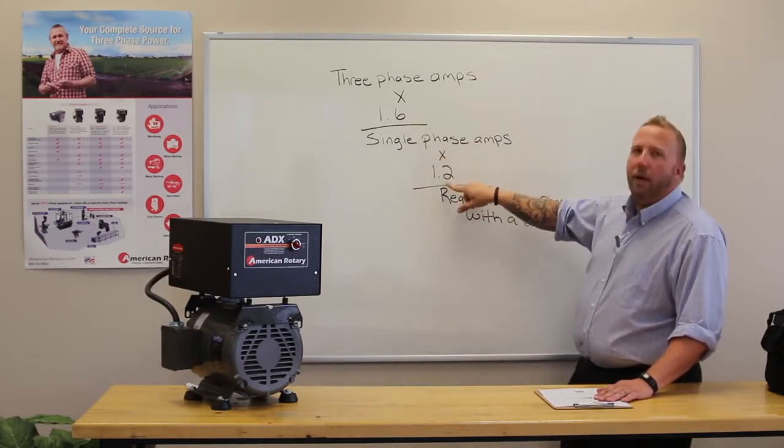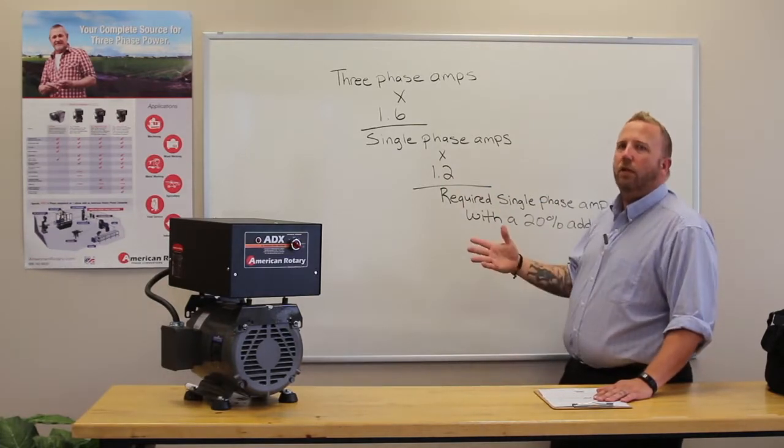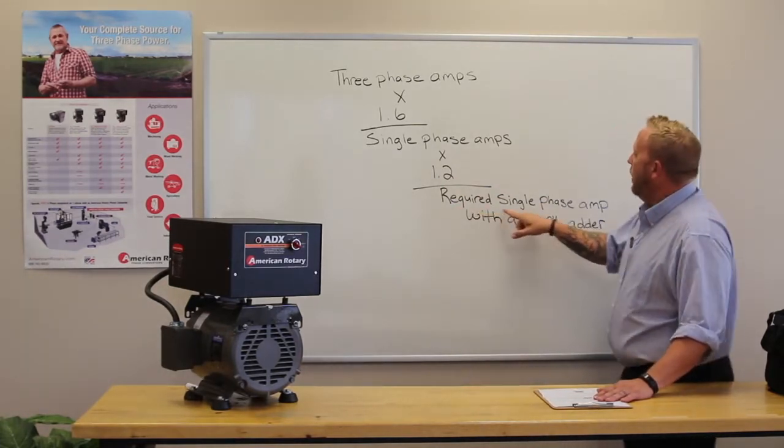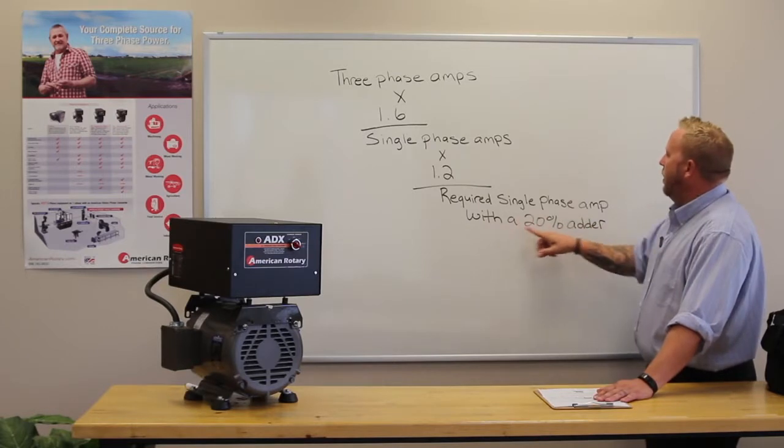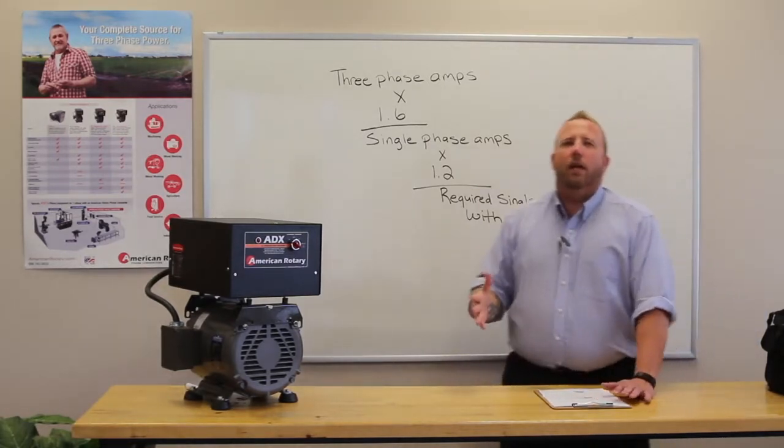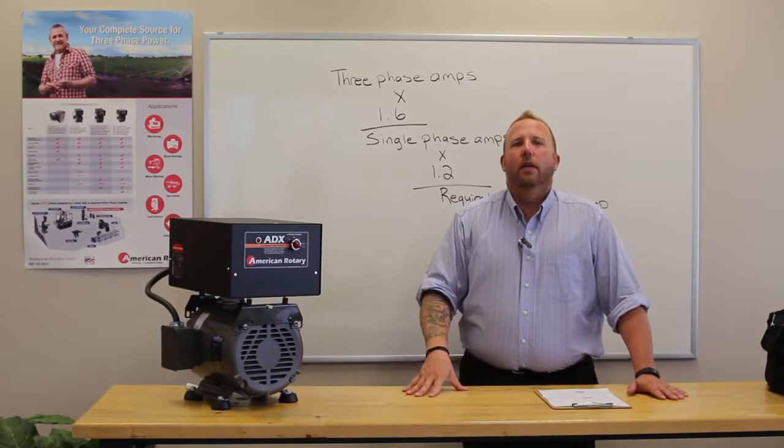You multiply that by 1.2, that's 20% above what your load is, and you're going to get your required single phase amps with a 20% adder. Why do we calculate in that 20% adder, you ask?